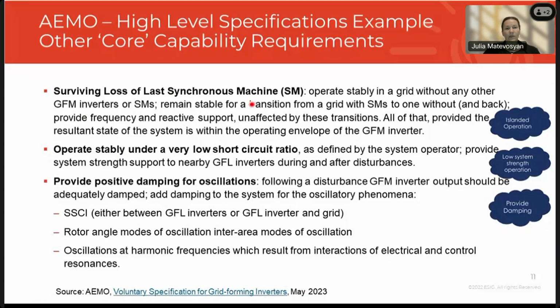And this is not to say that a single grid forming inverter should be capable of maintaining stability in an arbitrary island. Rather, in a test that is dimensioned specifically for the grid forming resource under test, if you trip the last synchronous machine and it is dimensioned to support the remaining load, it should stably do so and switch on and off from being operated as an island without synchronous generators to being operated back together with a system that has synchronous generators on it. It should operate stably under low system strengths, and then provide positive damping to oscillations. And they have a list of oscillatory phenomena where they are seeking help from inverter-based resources.